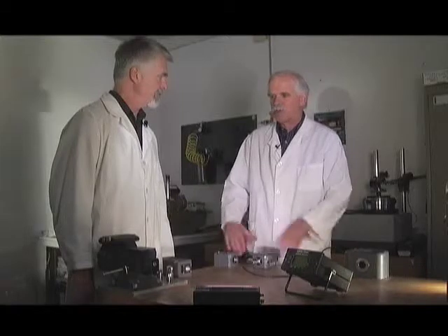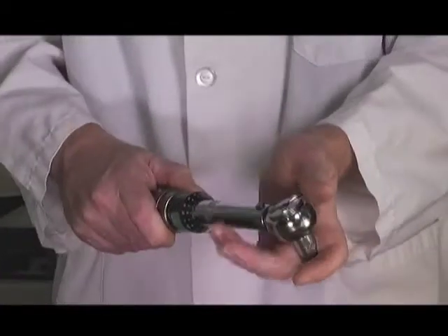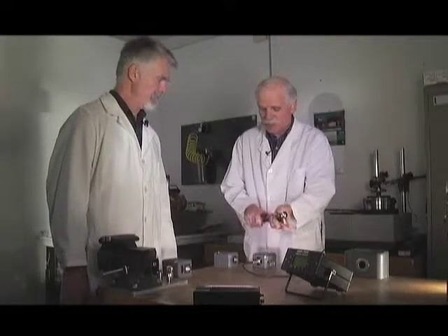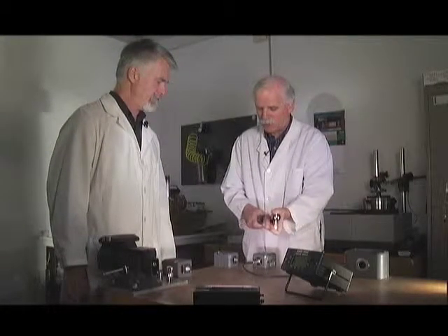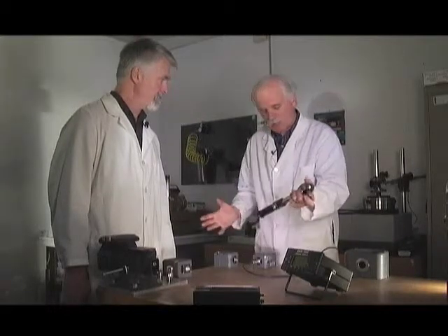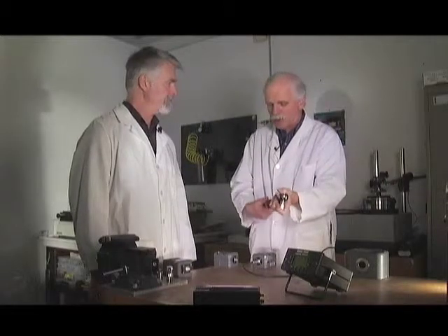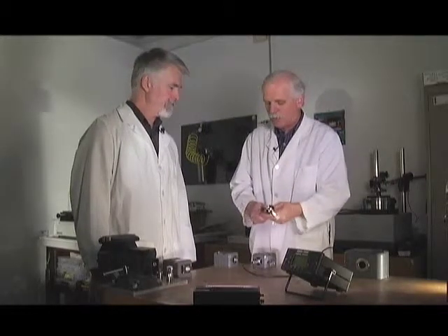Now, why do you click it 5 times before? That's just to release any internal friction, any dried up grease, anything inside of it. So as we mentioned, this is a spring-loaded device. You never leave it set to the number you're at overnight. Any spring-loaded device does not like to be left compressed. You'd always release it all the way back down to the lowest setting.